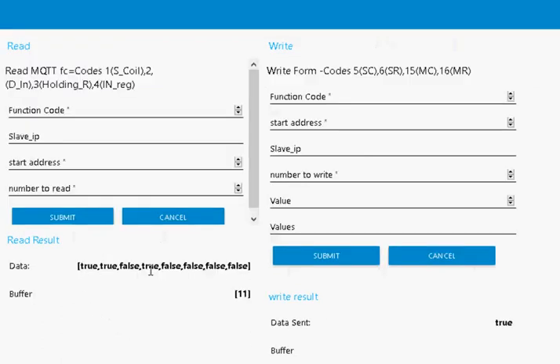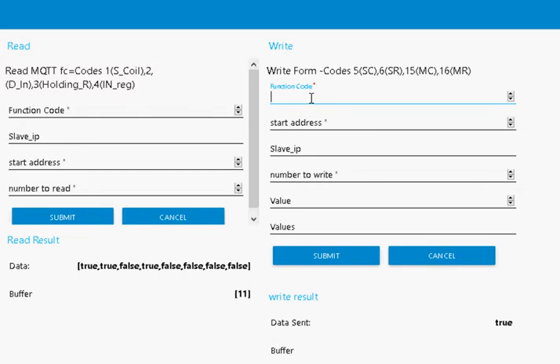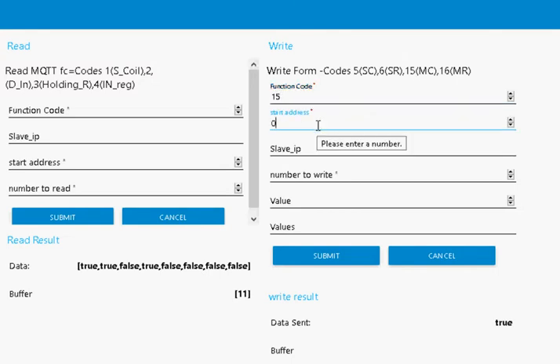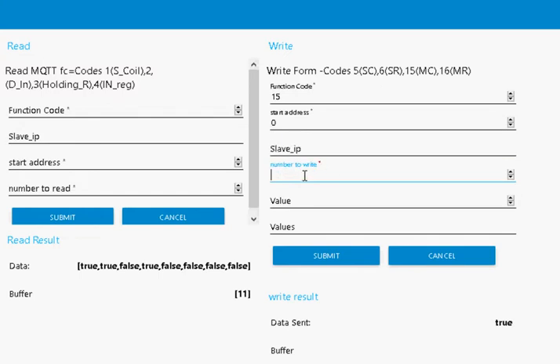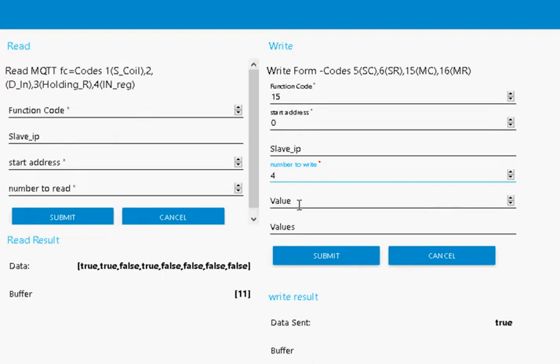Now we can also write multiple values, and we can do this with coils and with registers. I'm going to show you with coils. Multiple coils is 15, so I put function code 15 in here. Start address 0, don't need the slave. We're going to write, this time we're going to write 4. The values we're going to put in square brackets: we're going to write 0, which is false, 0, 0, 0. We're going to write all 0s.